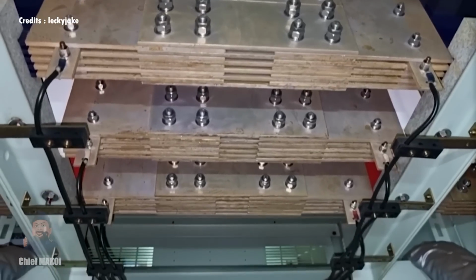On some ships, bus ties are a set of plates that are bolted on to link both sides of the bus bar. The only way to disconnect them is to intentionally shut down the generators and black out the ship, after which you have to loosen the bolts and remove the plates. To be honest, in all of my years of working on board a ship, I have never seen this being done except in dry dock when some additional components were installed or modifications were made on the switchboard. But I guess the simplest answer would be because regular cargo ships are not required by any regulation to do that. Hence, the design of having bus tie plates instead of breakers installed on many ships. Take note, I mentioned regular cargo ships.